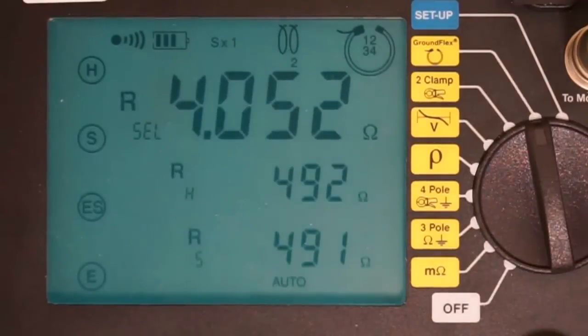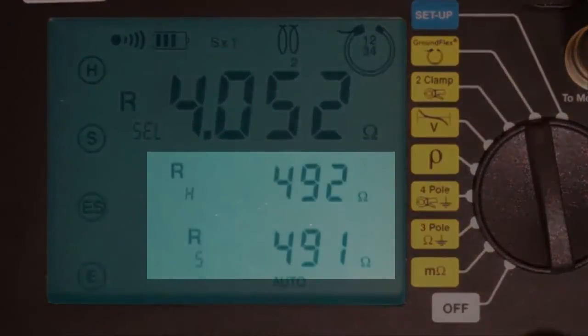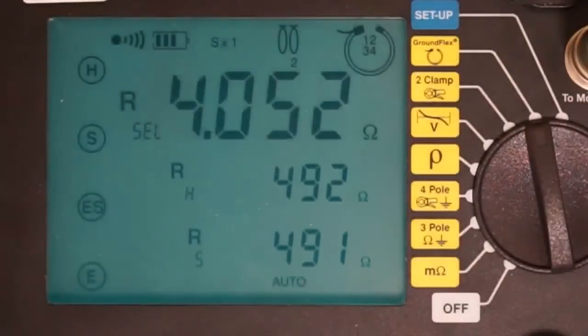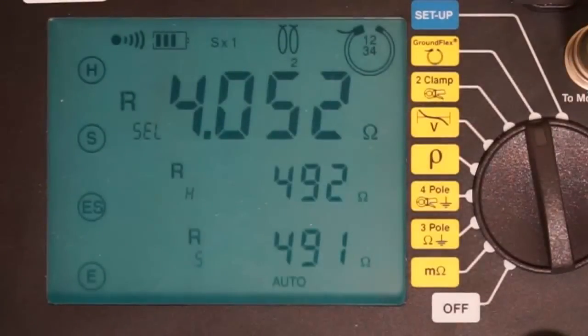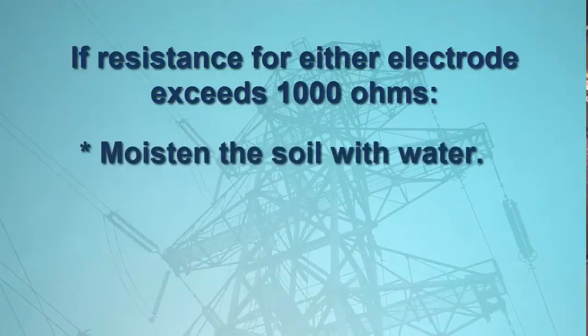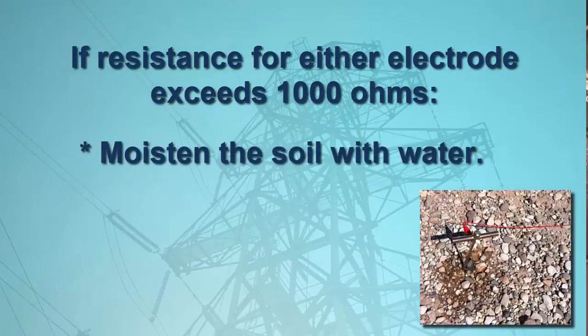Note that this screen also shows the resistance measured between our output probes and ground electrodes. For each electrode, resistance should be below 1000 ohms, as is the case here. Resistance higher than 1000 ohms can call into question the integrity of the measurement results. This is because resistance determines the test current, and too low a current makes obtaining reliable results difficult. In this situation, an indicator consisting of greater than and less than symbols may flash, informing you that the measurement may be unreliable. If the resistance for either electrode exceeds 1000 ohms, you can moisten the soil around the electrode by pouring water on it, and then retesting.